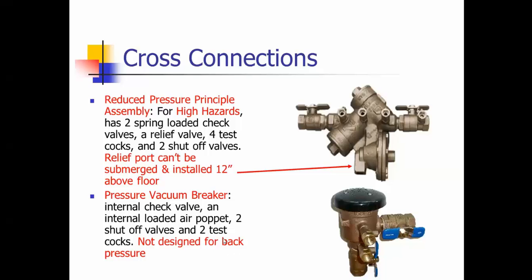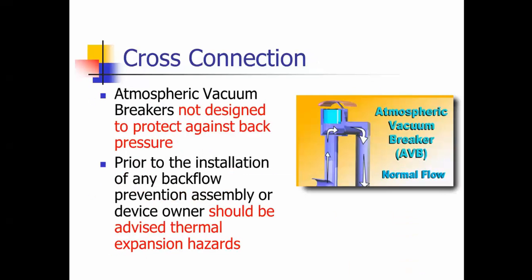A pressure vacuum breaker has an internal check valve, an internal loaded air poppet, and 2 shutoff valves, and there's 2 test cocks to test it. They are not designed for back pressure. An atmospheric vacuum breaker is likewise not designed to protect against back pressure.